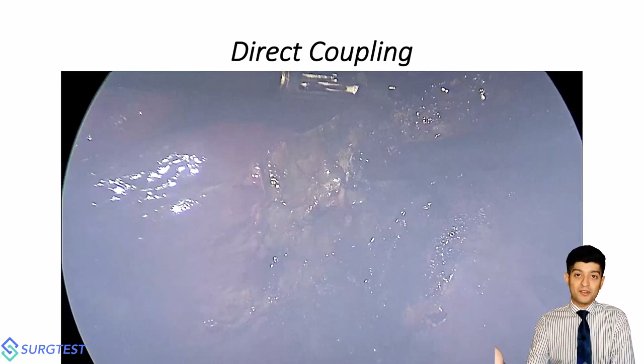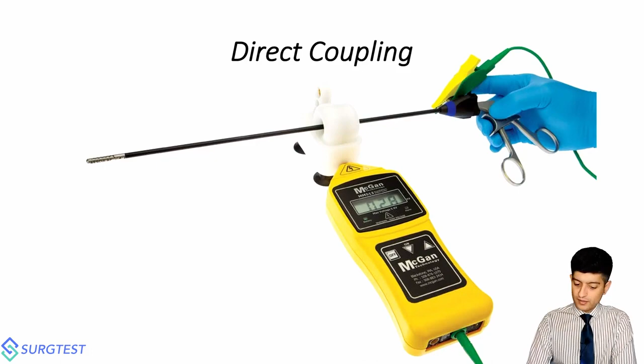To check the insulation of devices, you have these insulation checkers. You essentially connect a monopolar current across the device, and you pass the device across this little loop that is present over here, and it checks if any current is able to spark across the insulation within this handheld device over here. So if any current is leaking, then that insulation needs to be changed immediately. Never use any lap instrument where the insulation is dicey. You may end up having energy related injuries very far away from where you're actually working in the surgical field.